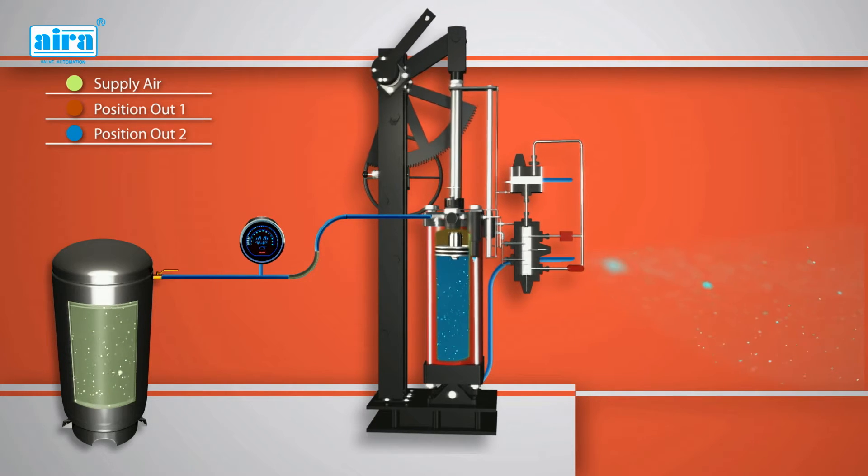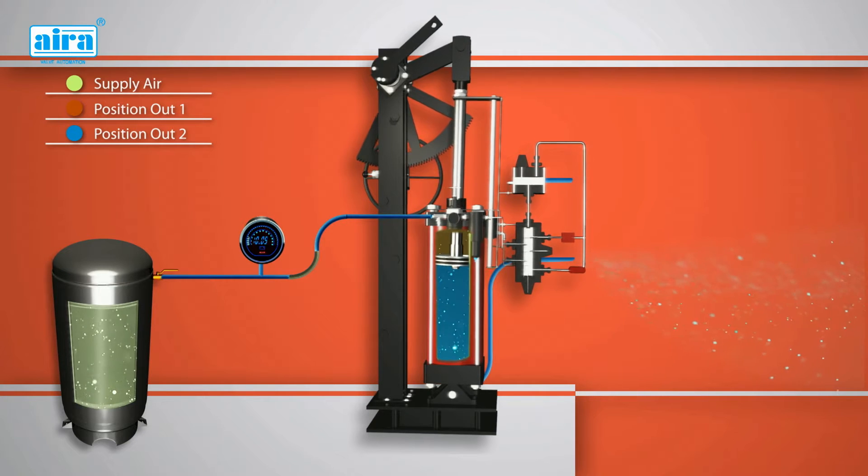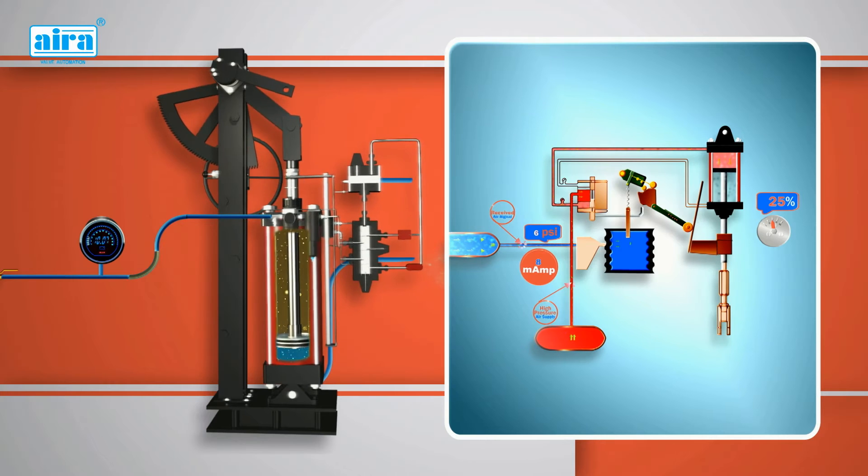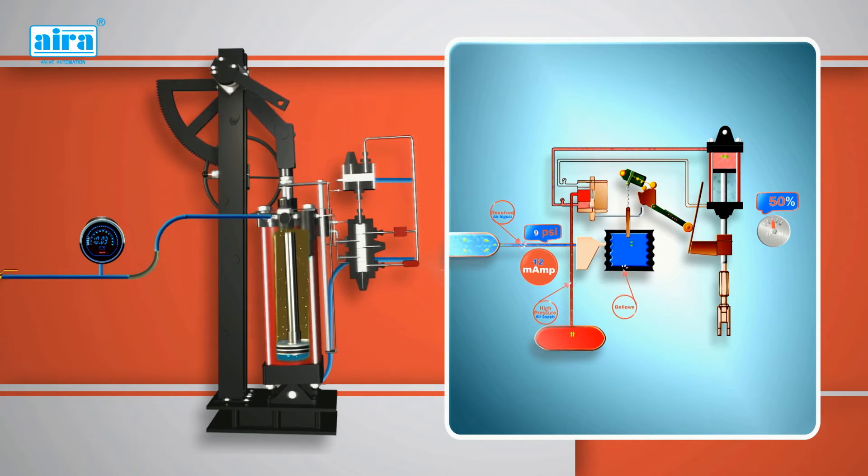Let's see how a power cylinder works. The position control unit incorporated in the power cylinder receives air signal from a controller and regulates the high pressure air supply to the cylinder to give a corresponding displacement of the piston.